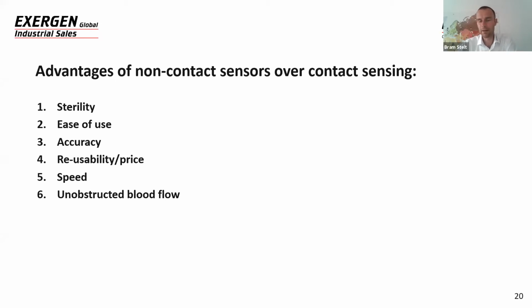First of all, sterility. If you supply anything to a patient, blood, it needs to be sterile. So you don't want to put anything in the blood that could potentially cause an infection or contaminate it. With our IR sensors, there's no contact with the blood whatsoever. The ease of use, as I demonstrated in the rapid infuser: if you install the sensors in the body of the device and you design it in such a way that you can click on a cartridge, it's really easy. Click and it goes. The sensors will give you good results and measure temperature accurately and reliably. Whereas if you have a contact probe, it always requires manual handling, attaching it, putting it through valves. That's not easy to use.